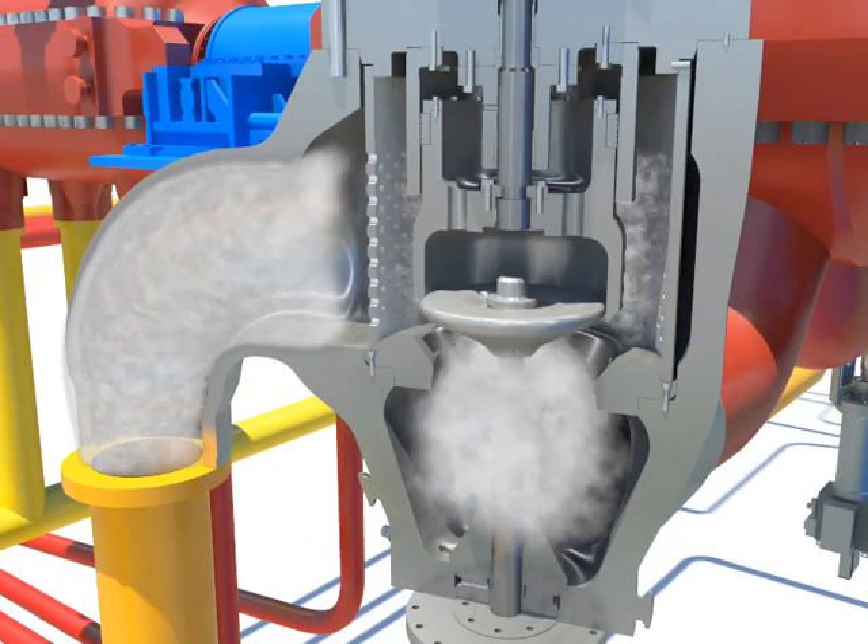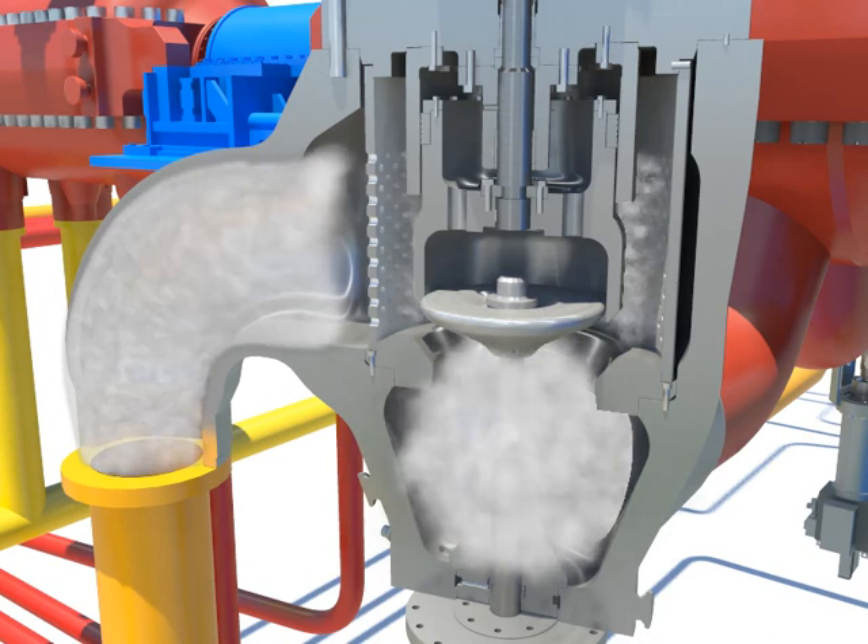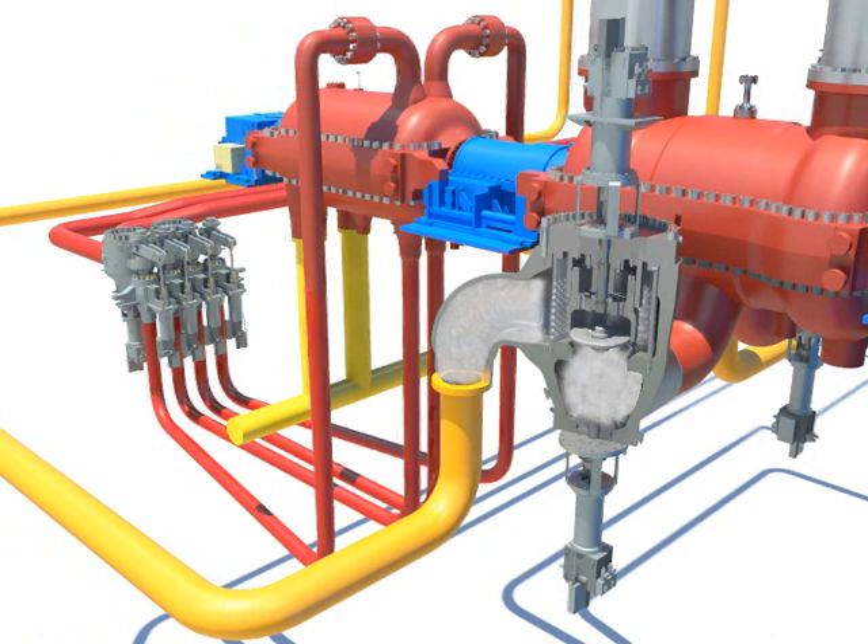The reheat steam goes into the entrance of the intermediate-pressure turbine after going through the strainer, intercept valve, and stop valve's disc. When the valve closes, it blocks the steam by closing rapidly by the spring compressive force due to the pressure loss of the control oil or cutting off.